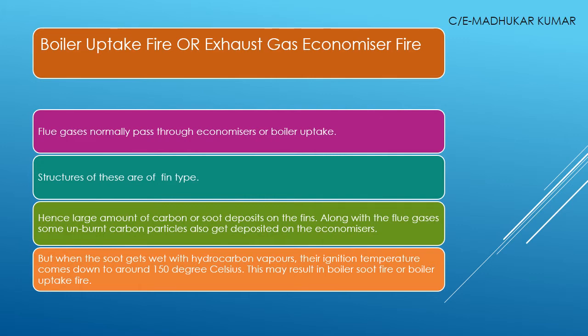When this soot combines with hydrocarbon vapor, the ignition temperature comes down to about 150 degrees Celsius. So as the ignition temperature comes down to this range, the boiler soot catches fire. The self-ignition temperature of soot is normally on the higher side, but along with the unburned carbon particles deposited with the soot, this lowers the ignition temperature down to 150 degrees Celsius — and then the soot fire starts.